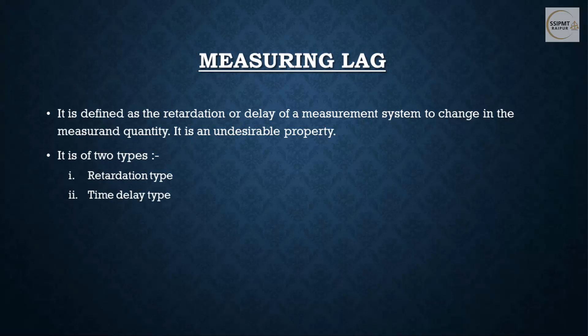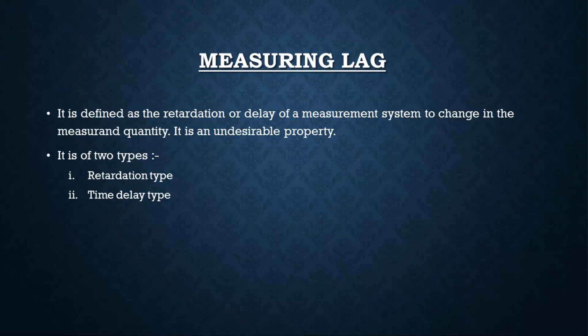So the measuring lag is of two types. First, retardation type. Sometimes you are giving input and your output is not coming, your instrument stops. Similarly, your instrument is taking much more time for giving you output, that is time delay type. So this characteristic is known as measuring lag, and it is an undesirable property. An instrument should not have measuring lag.